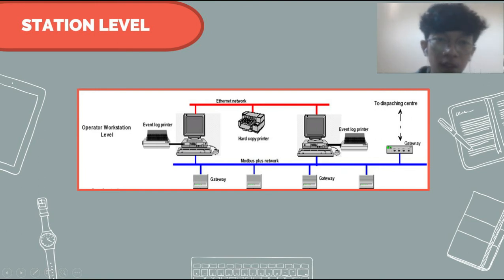In addition to the scanning system, data exchange can also occur incidentally. For example, when the circuit breaker switch is closed by the substation operator, the RTU will automatically and immediately send the CB status at the substation to the master station. The dispatcher will immediately notice that the CB has been closed.